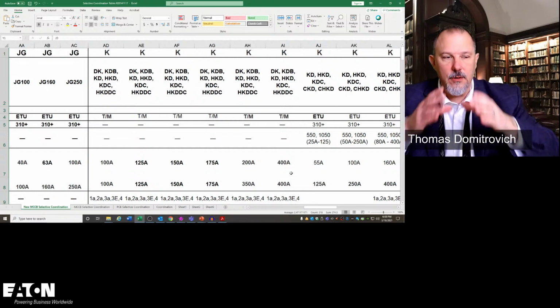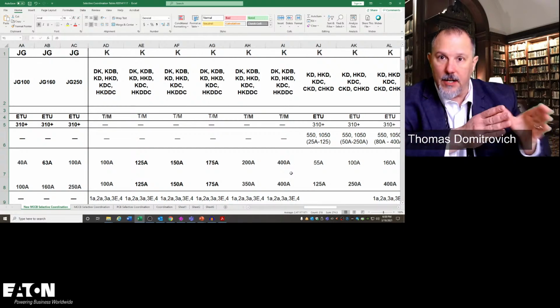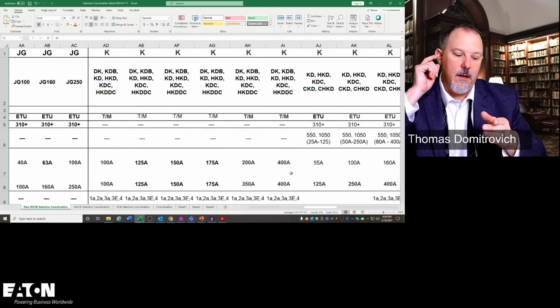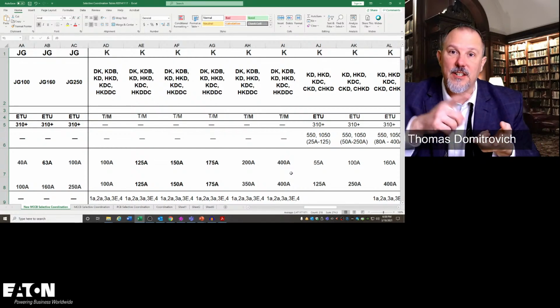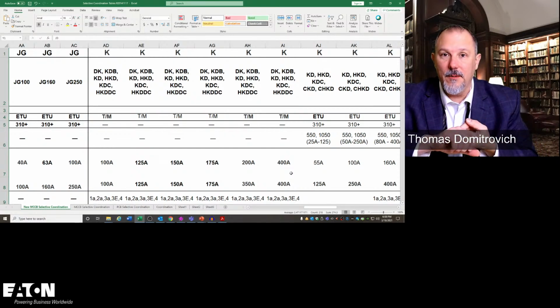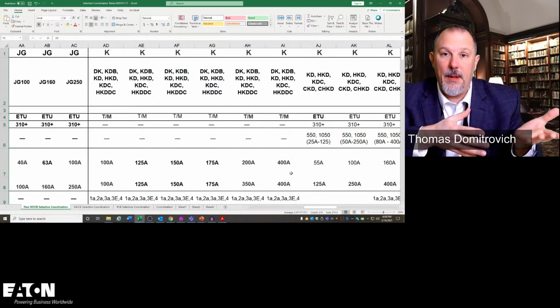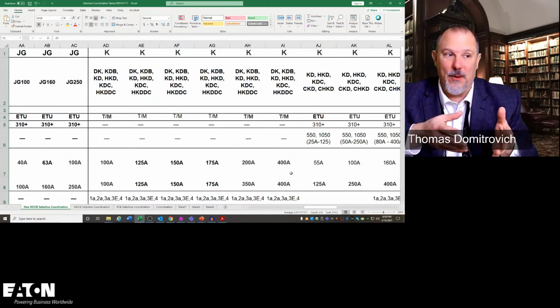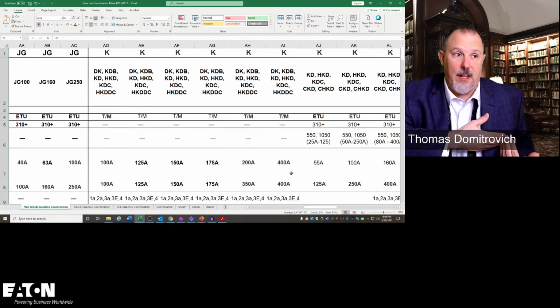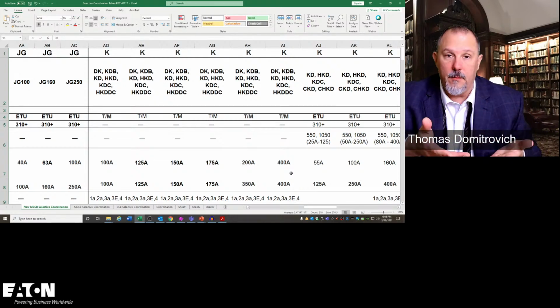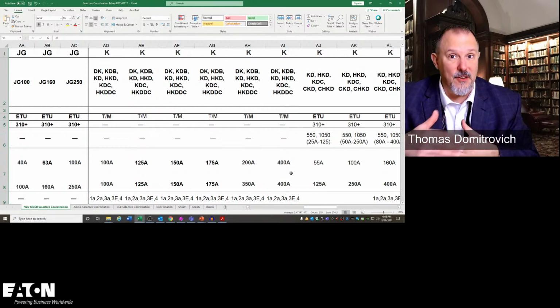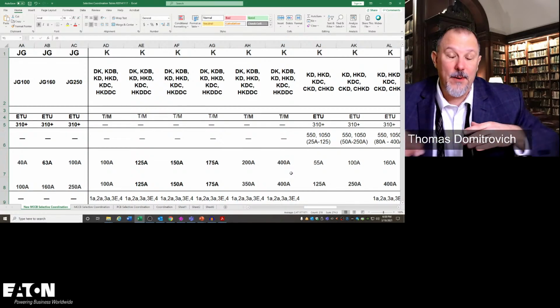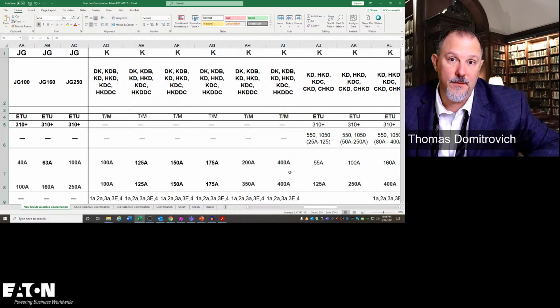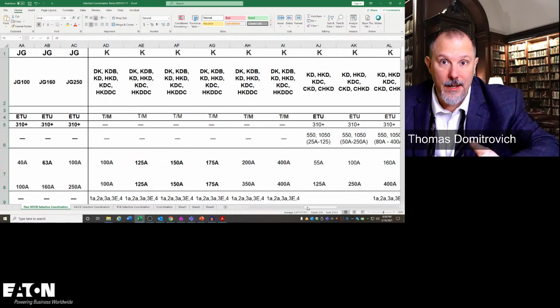So not only did I increase the size and the cost of that breaker, I've increased the conductor, I've increased the raceway, because whatever conduit I picked, the size of that might not be adequate for 400 amps worth of conductor as opposed to 250. So now I got to pull different pipe in, and hopefully I didn't find this problem after the fact. And oh, by the way, I can't use a 250 amp panel board. I got to use a 400 amp panel board. The cost of my system went up considerably, but that's for somebody who doesn't know what they're doing.